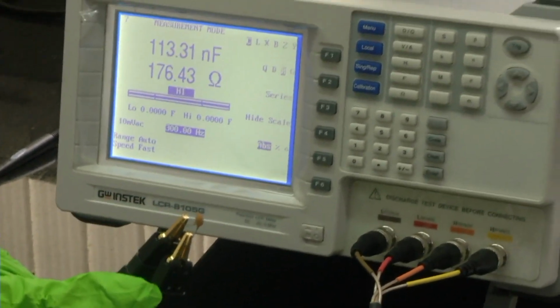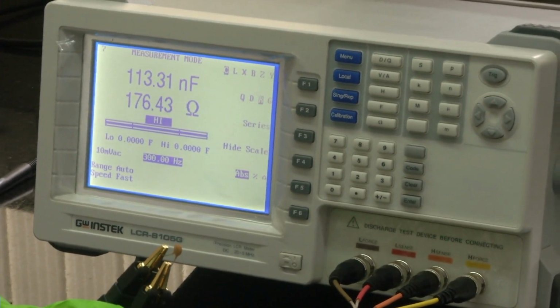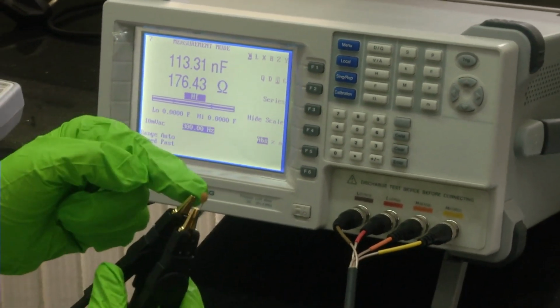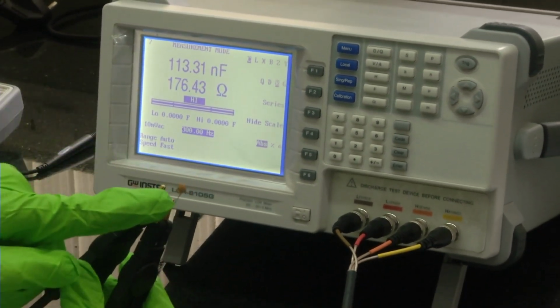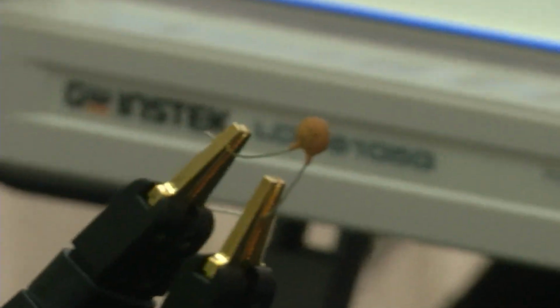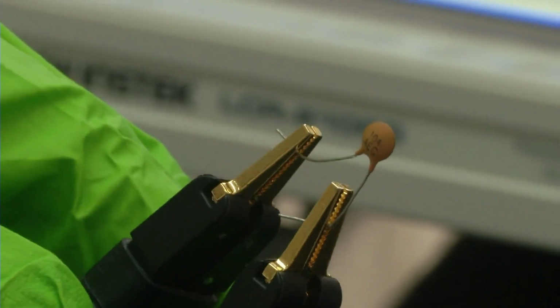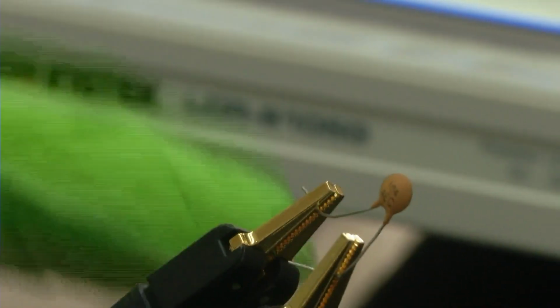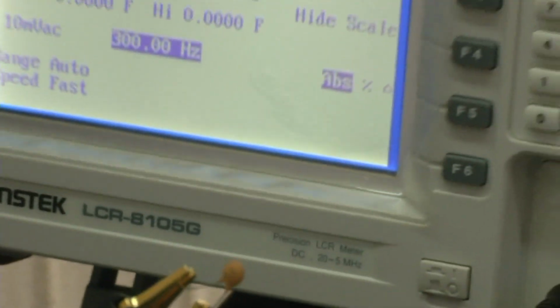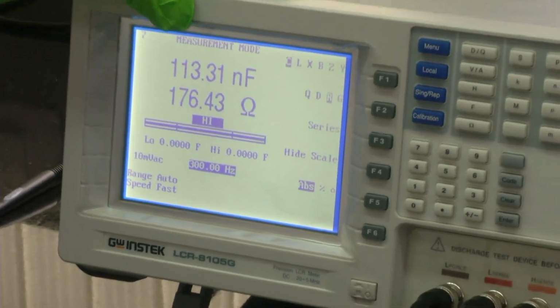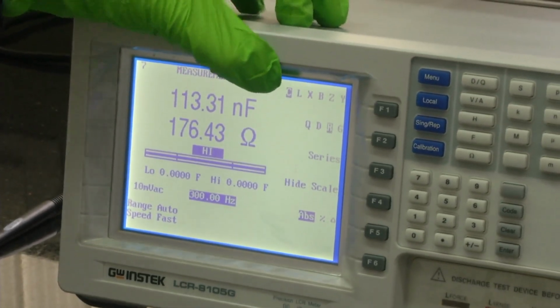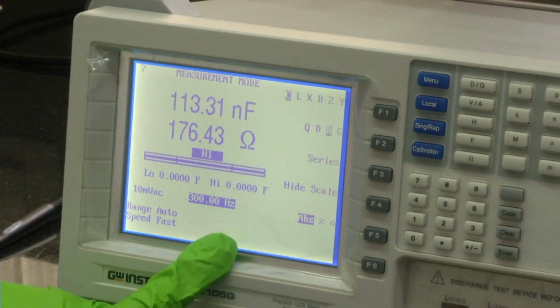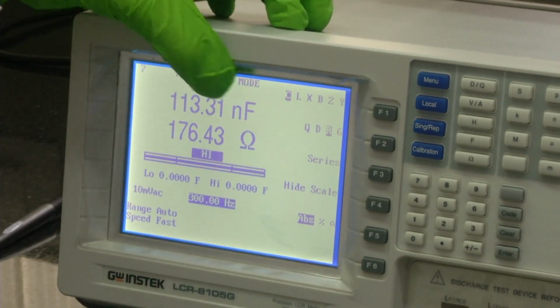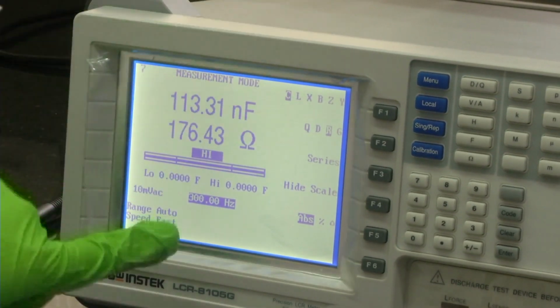So, you see the probes, and we have connected a capacitor to the probes. This is a 0.1 microfarad capacitor. Hope this is clearly visible to you guys. Now, I have connected the probes. In the measurement mode on the screen, if you see, we have kept it in capacitor mode and we have kept the frequency as 300 hertz. It will show the capacitor value and the impedance at that frequency.